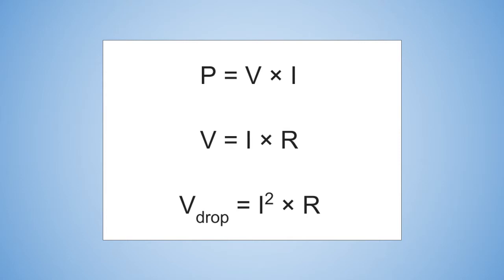Now that we understand this, let's get to the losses. We calculate the voltage drop by the formula V drop equals I squared times R. Often I am told that DC current has higher losses than AC, and that is why DC power systems lost the battle. That's not true at all. Please tell me where to plug AC or DC voltages into the formula V drop equals I squared times R.